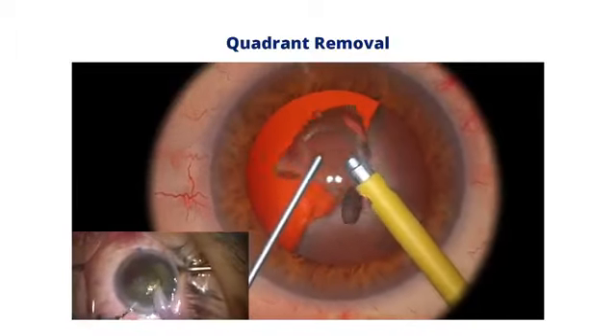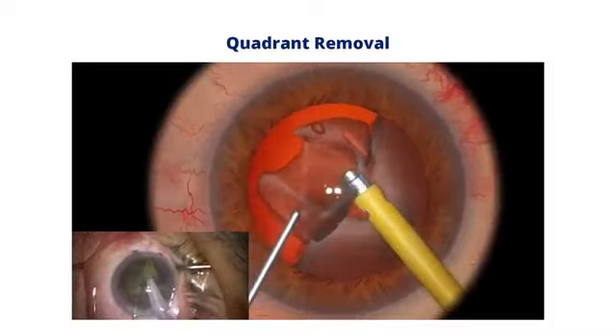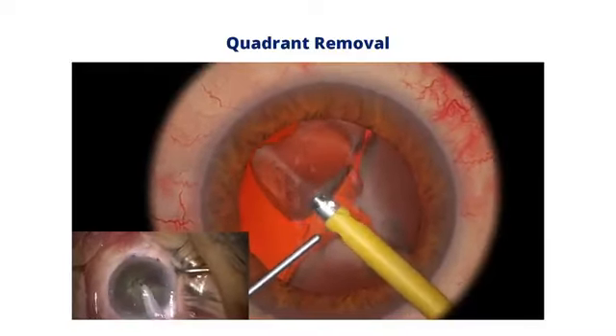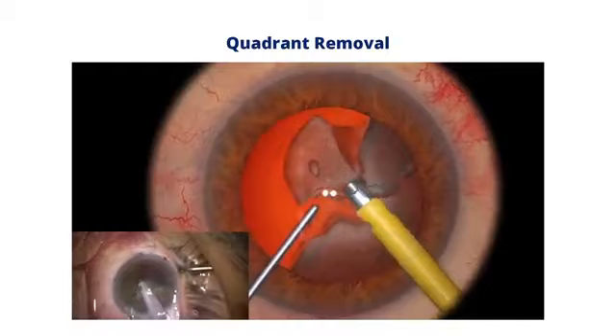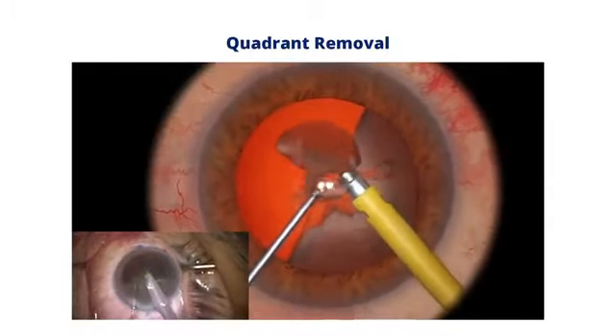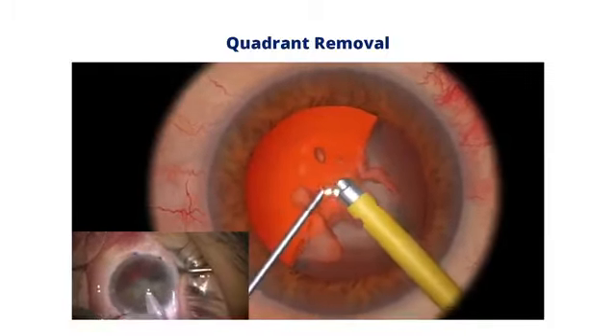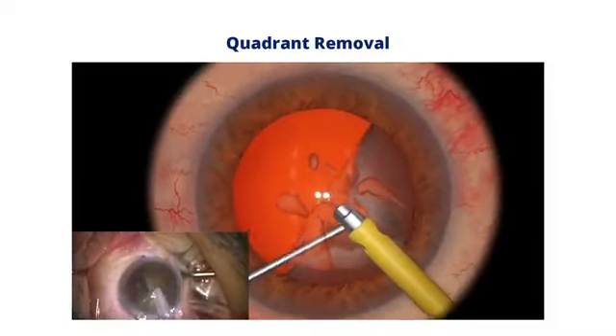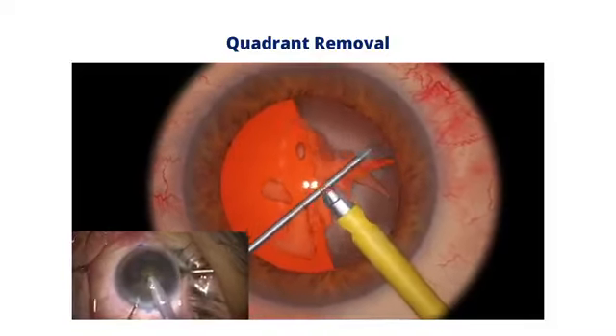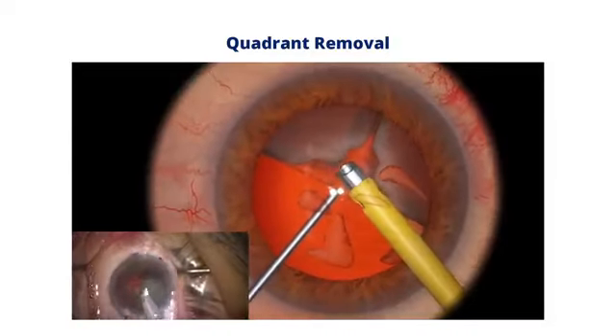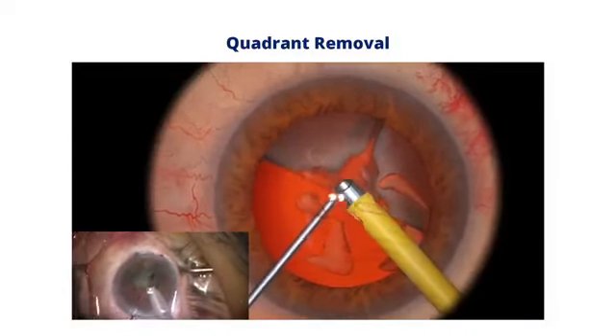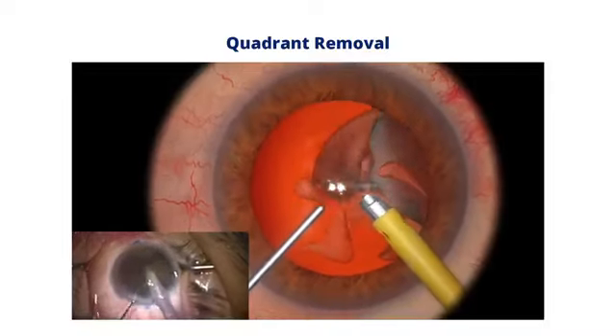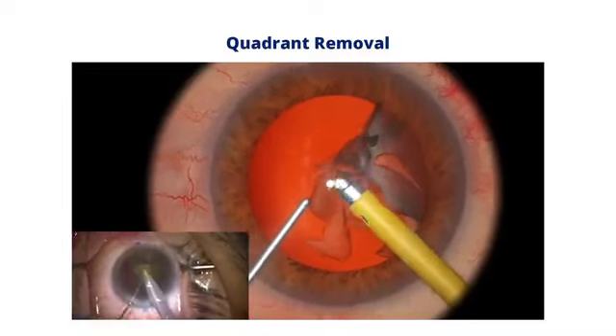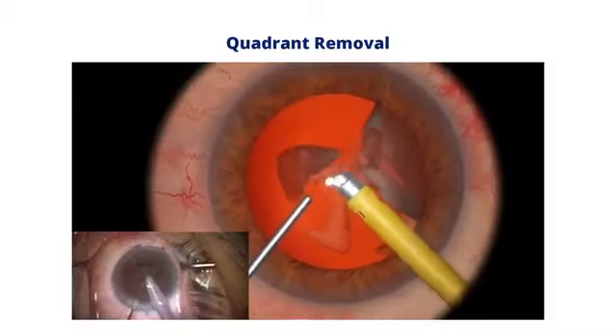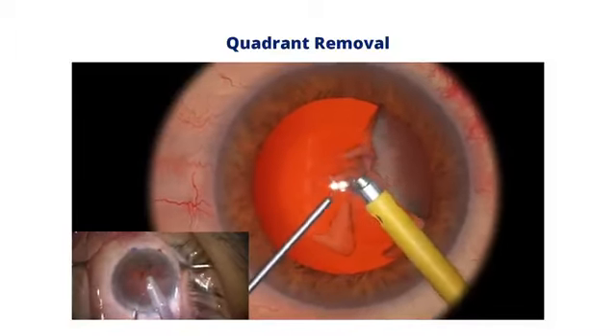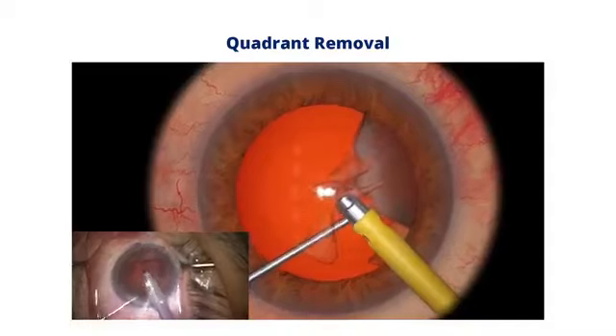The first fragment may require some control and manipulation to bring forward, away from the other fragments, particularly if the nucleus is dense. This control requires occlusion of the phaco aspiration port and high vacuum. A brief burst of phaco power will be required to gain occlusion so that high vacuum can build up. Once this has been achieved, no further phaco power is used, i.e. the foot pedal stays in position 2 as the fragment is pulled into the safe zone. Short bursts of phaco power combined with aspiration can then be used to remove the fragment.